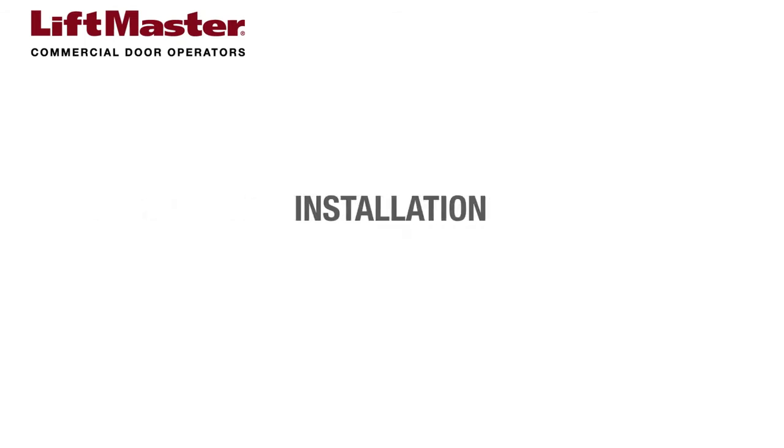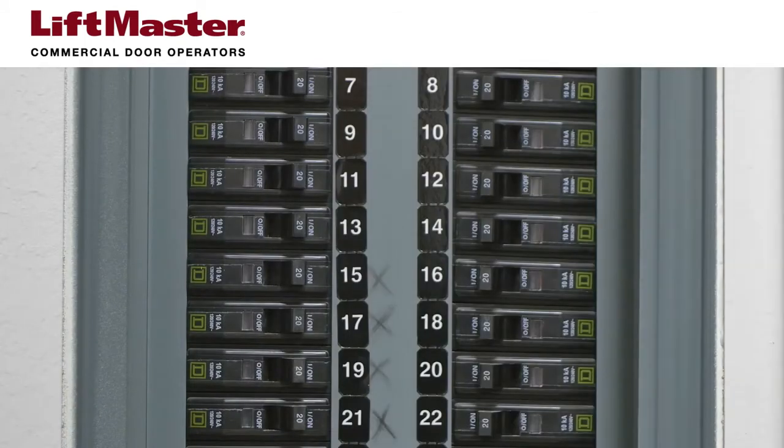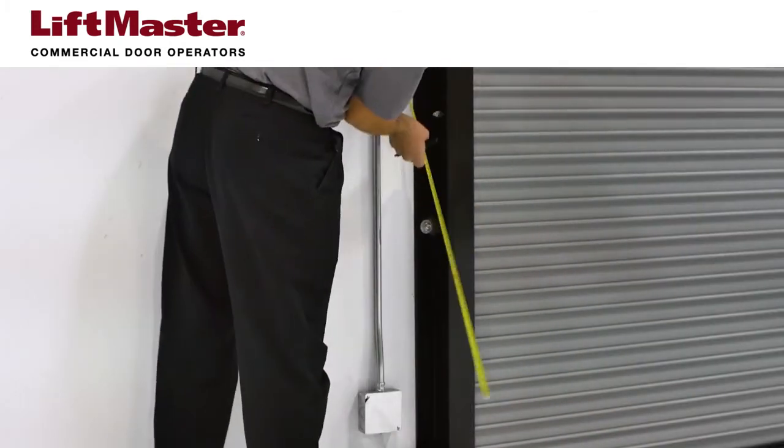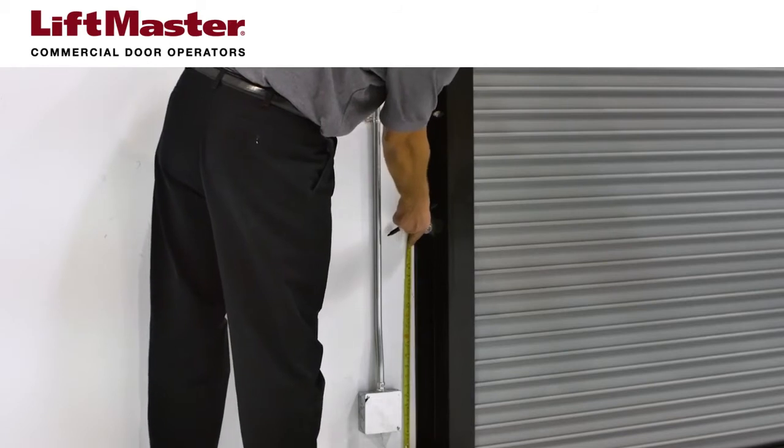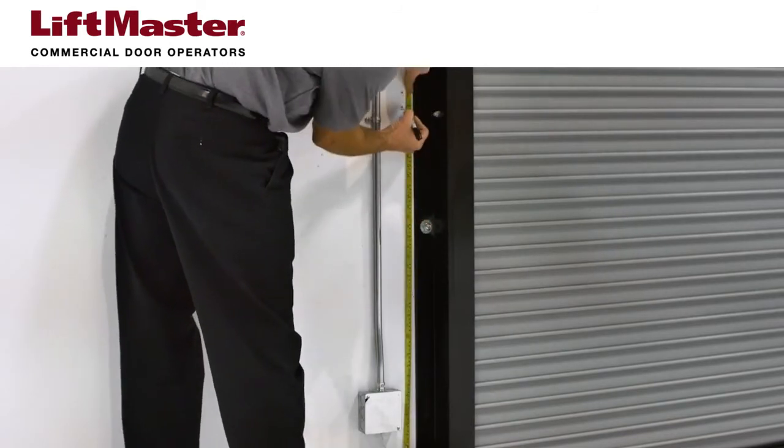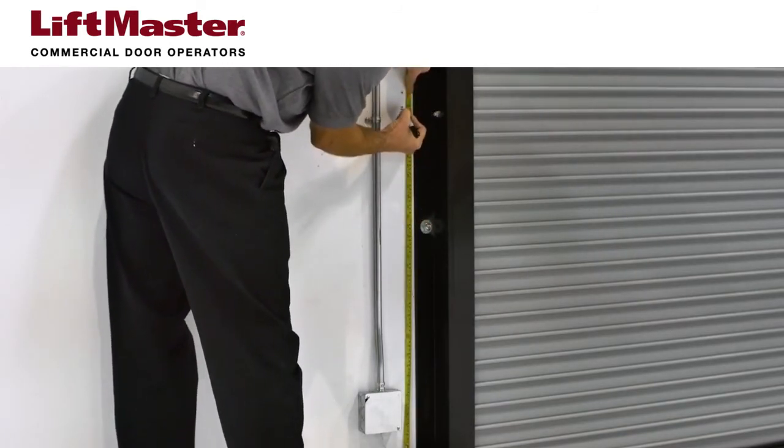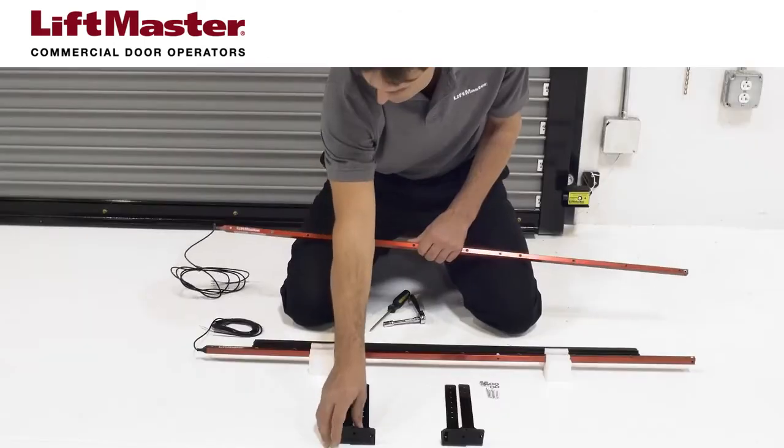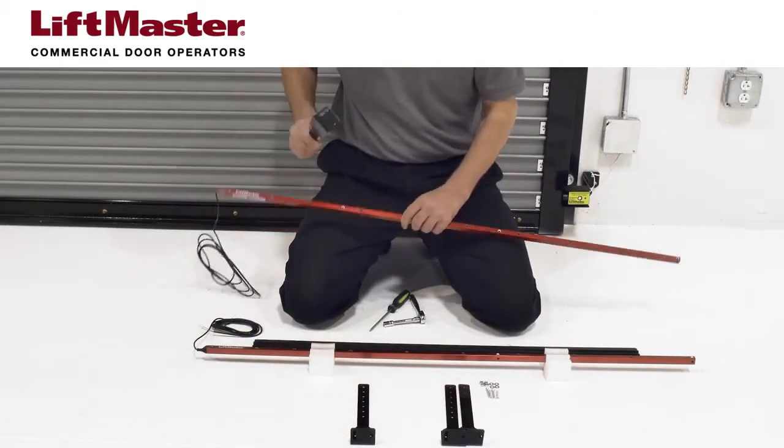Installation. Begin by disconnecting power to the operator. Light curtains must be installed a minimum distance of 12 inches above the primary photoelectric sensors. We've already measured and pre-drilled mounting holes using wall anchors as appropriate.